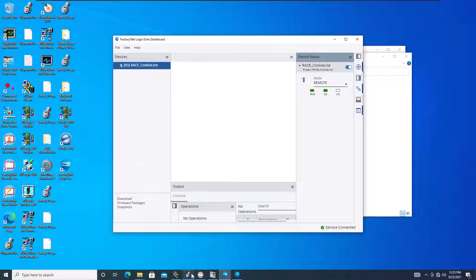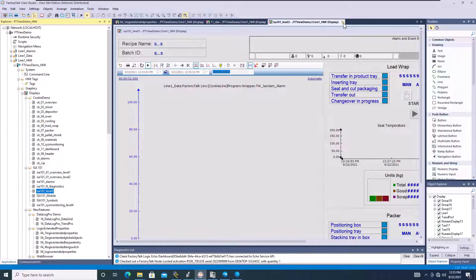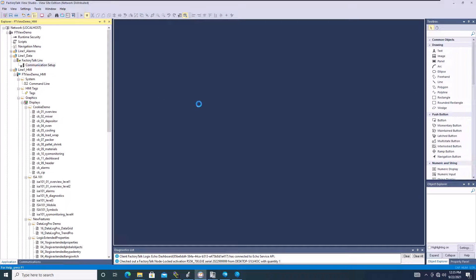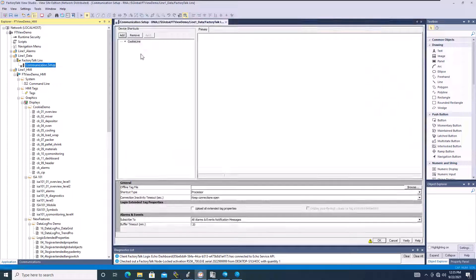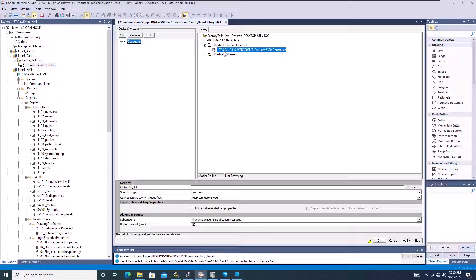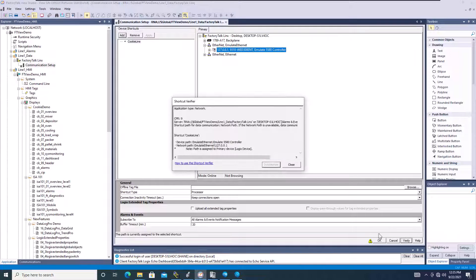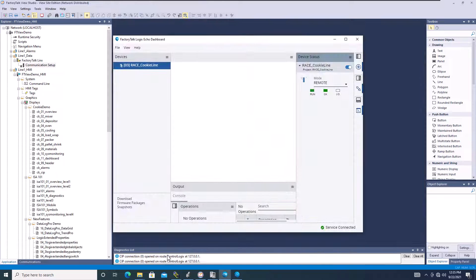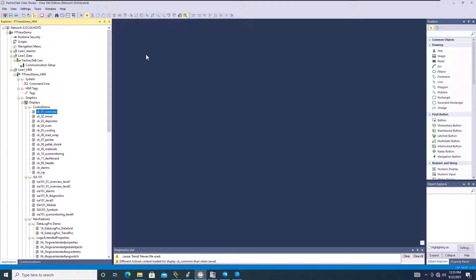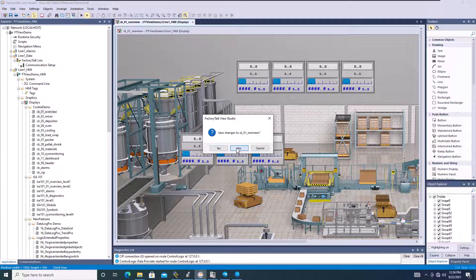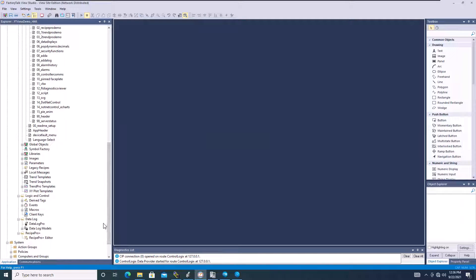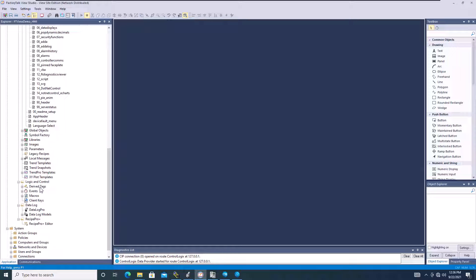Let's go back to Factory Talk. After we get our HMI working, we'll go to FactoryTalk Linx communication setup and point it to the path that we designed for it. We're going to get the cookie line and go down here. It's already set as they have tested before, so it's set properly. We're going to verify, hit OK. Once we do, it's going to connect. We do have a connection. We can open this up to test to make sure we have connectivity. We do. So now we can run the client, see how it works, and then get back in the design and see how the software changes are implemented.